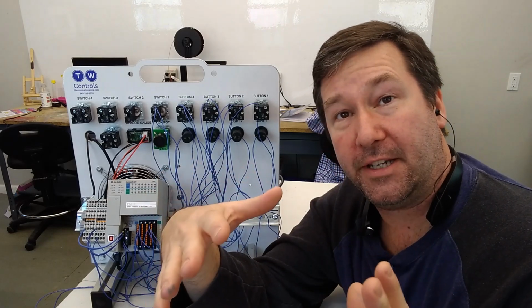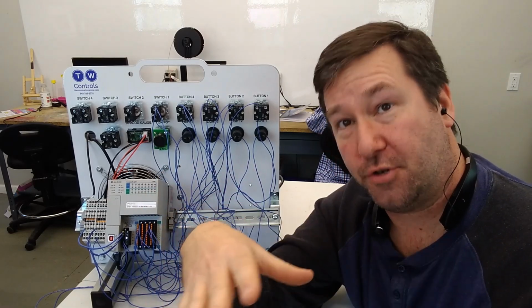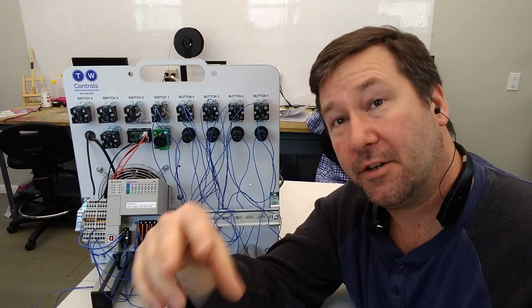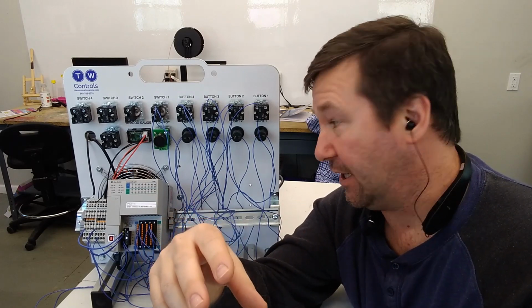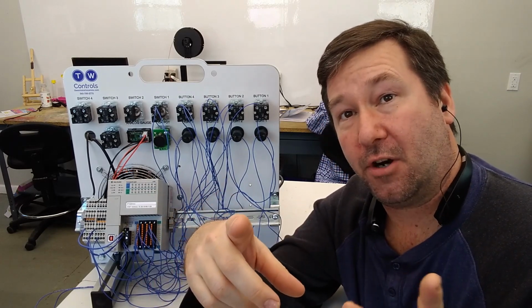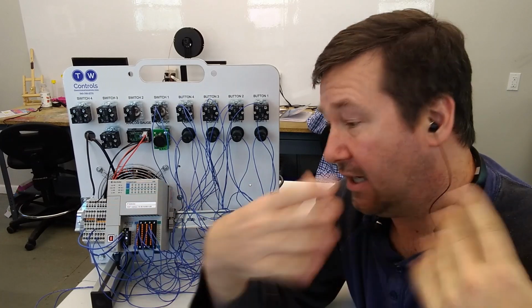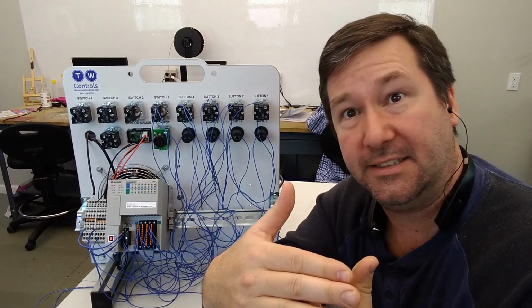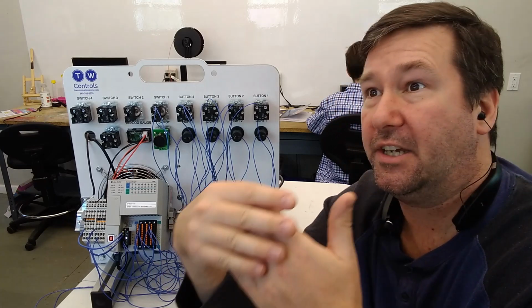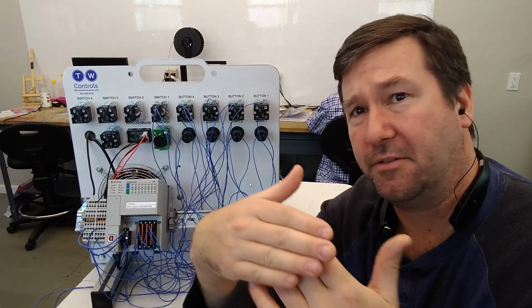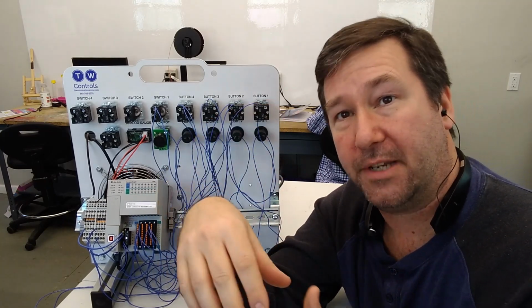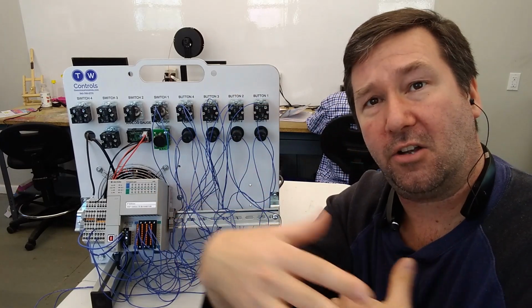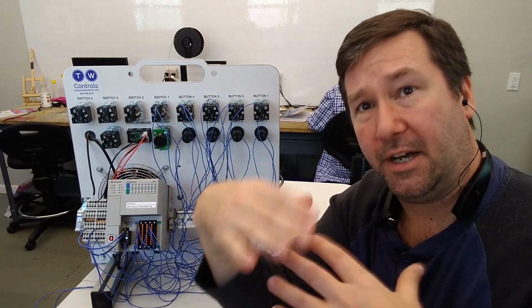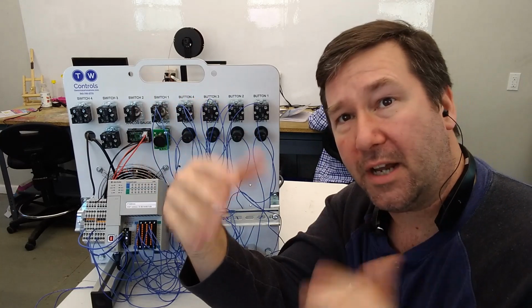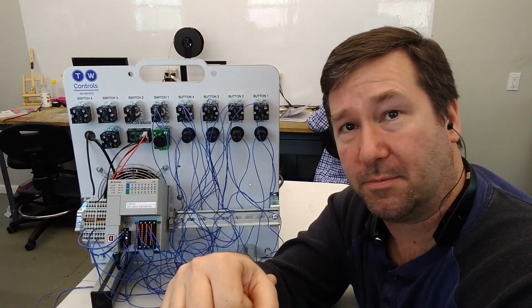So if you're having headaches like this and you're sure that you have your drivers configured properly, then try deleting those two Harmony files. It won't hurt anything. As soon as you open RsLinx back up, it's going to create those files again, and you'll be up and running. Mainly all your other history, like, say you've been to the last 100 PLCs that are normally clogging it, all of that will be gone. But it'll get rid of whatever corruption actually causes this problem.